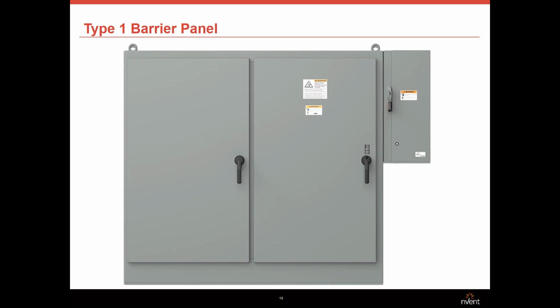With a UL Type 1 barrier panel installed, there will be 3 distinct enclosures to be rated in this illustration. Once an IEEE 1584 assessment of control enclosures has been completed, the enclosures will be labeled with the appropriate hazard warning label. Then the appropriate PPE required for the hazard in each enclosure is established.